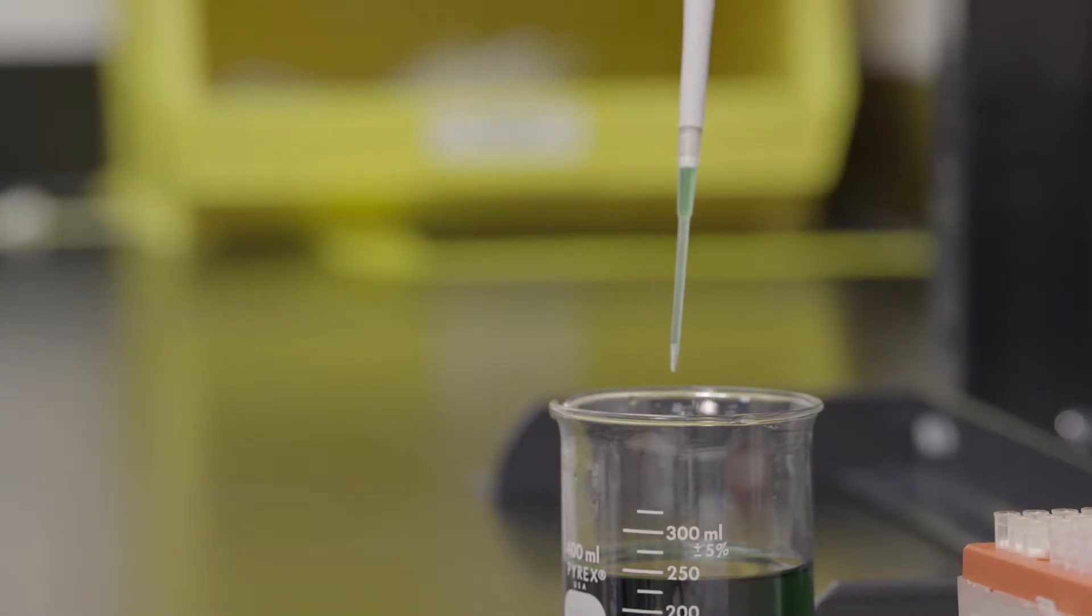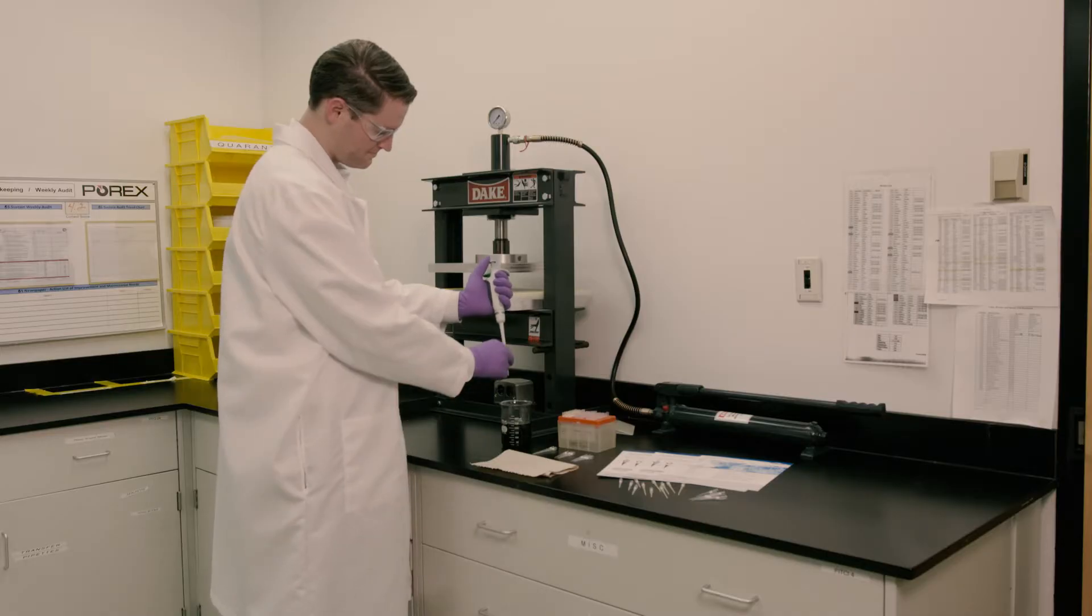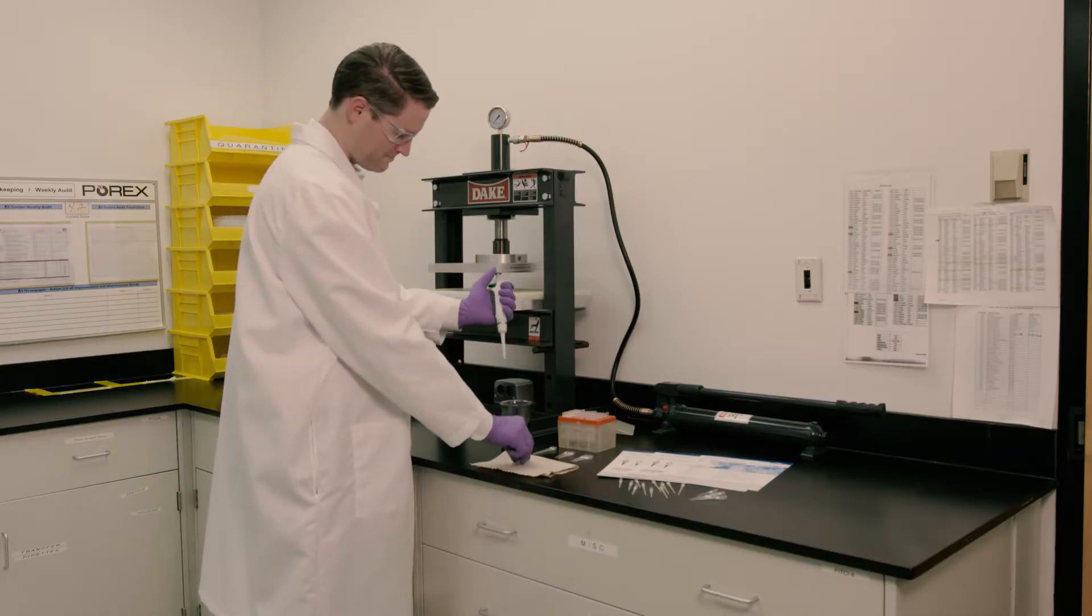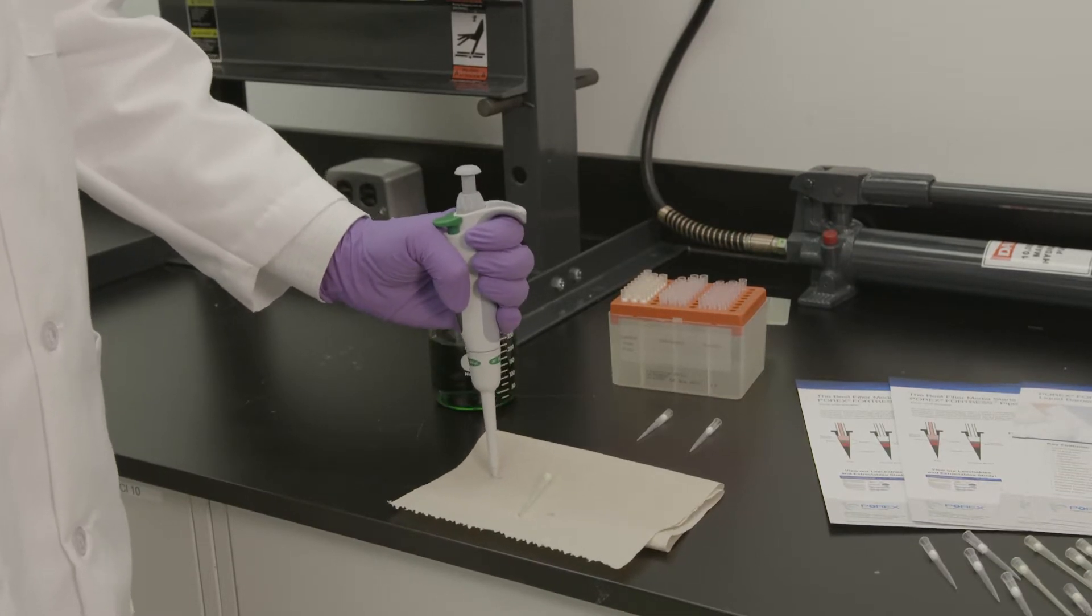The sample can be retrieved, but contamination is a possibility, along with the green sample being carried over to subsequent samples. Or, the green sample can be held in the pipetter shaft, thus contaminating the pipetter.